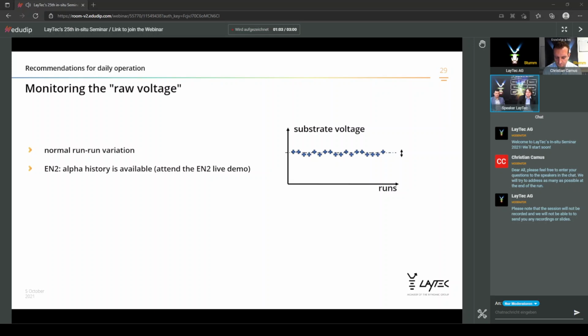So what we would expect, if the system alignment is fixed and correct and the viewport is clean from run to run, is a small fluctuation, but overall a straight line. You always have the same voltage since the optical path is the same. What we recommend is to insert a silicon wafer and open the window to check it. In the afternoon session, during the live demo of the EpiNet 2, Thomas Mann will show how to do that in the EpiNet 2 and to track it.